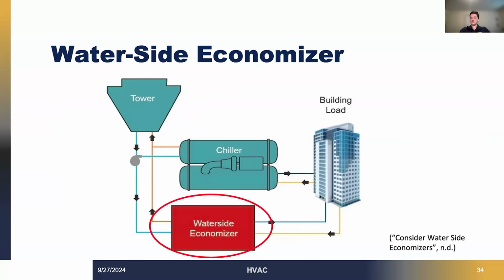Here's a diagram of a waterside economizer, and you can see that it combines all different loops within the building. This design features the capability to bypass the chiller, which is shown in the middle, enabling a heat exchange between the outdoor water tower's water loop and the building's water loop within the economizer. This heat exchange is crucial as it effectively prevents outdoor debris from entering the building's water loop, ensuring cleaner water circulation and maintaining system efficiency. By utilizing this innovative design, facilities can enhance their cooling efficiency while protecting their HVAC infrastructure.